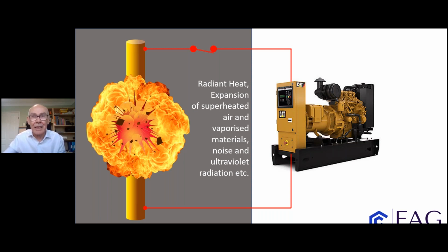It doesn't disconnect the circuit. It vaporizes, and in doing so it ionizes the air between the two conductors, creating a low impedance path. Large amounts of current flow immediately, creating temperatures as high as 20,000 degrees centigrade at the arc tips, which will immediately vaporize any element known to man, causing a massive expansion of air and vaporized conductor material - an electrical explosion.